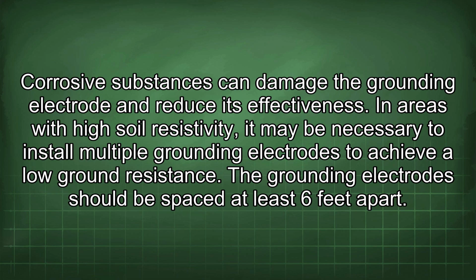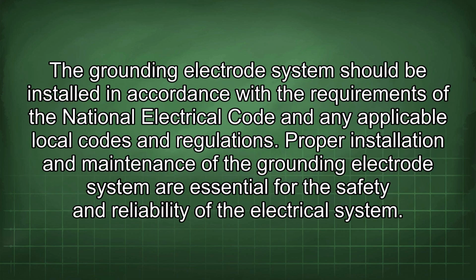In areas with high soil resistivity, it may be necessary to install multiple grounding electrodes to achieve a low ground resistance. The grounding electrodes should be spaced at least 6 feet apart. The grounding electrode system should be installed in accordance with the requirements of the National Electrical Code and any applicable local codes and regulations. Proper installation and maintenance of the grounding electrode system are essential for the safety and reliability of the electrical system.